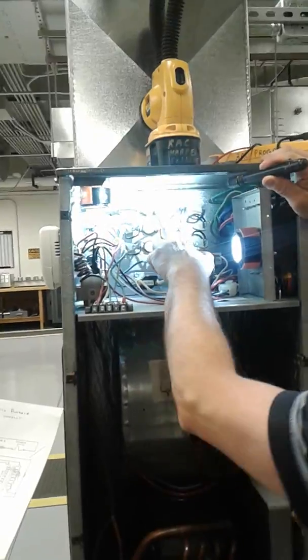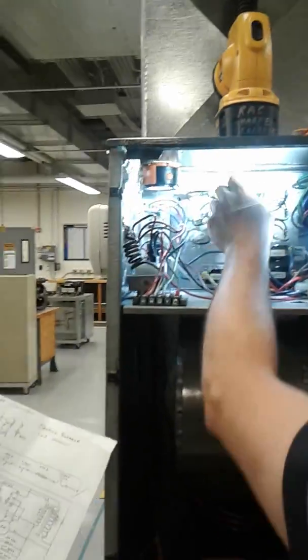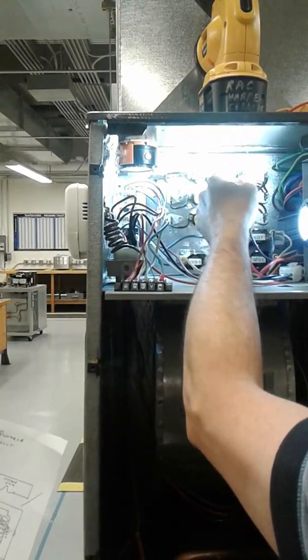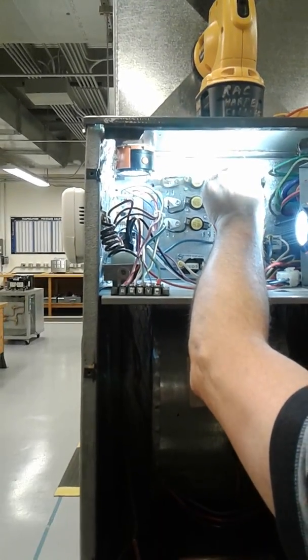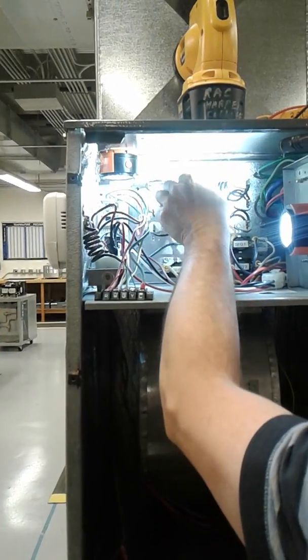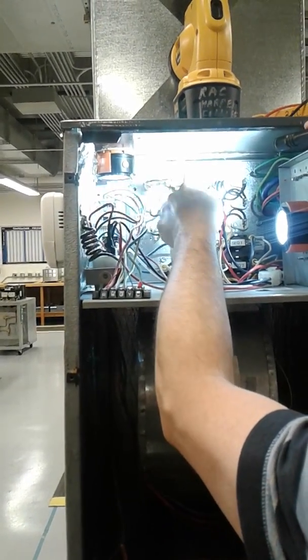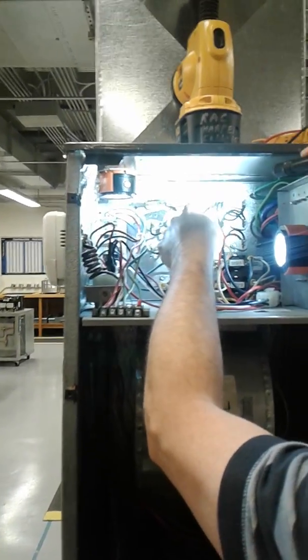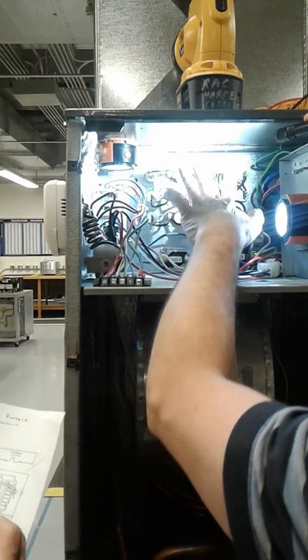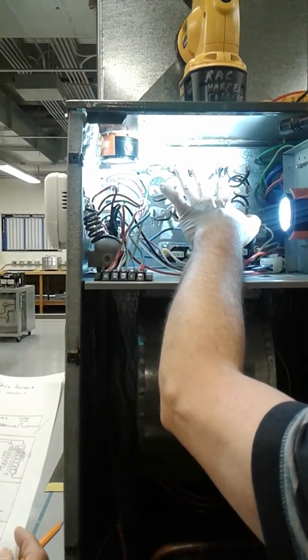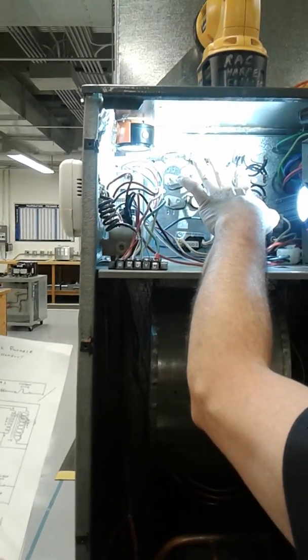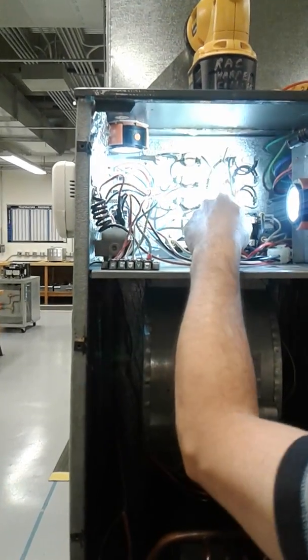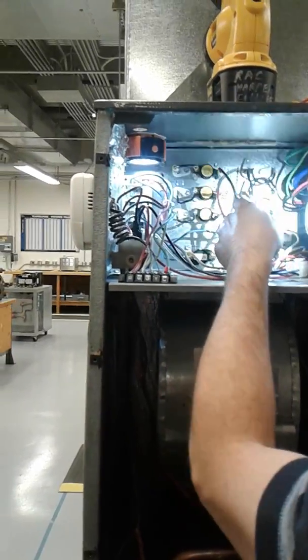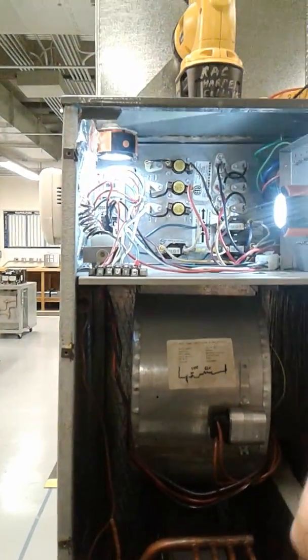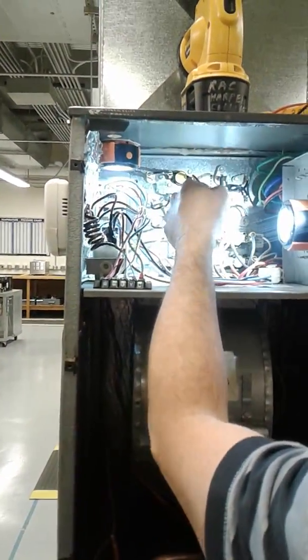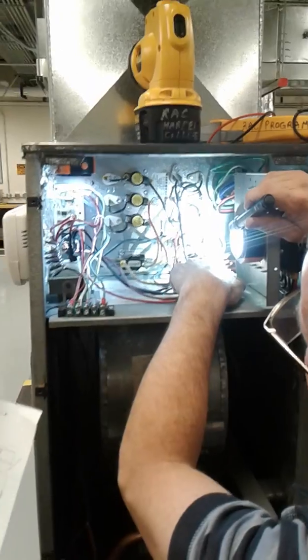Okay, now, the power that is entering element 1 are these two wires here, the two black wires. You've got 120 volts going in here to the fusible link, passing through the fusible link, going through the element. You have other 120 volts going in right here, okay? Being energized, going through the high limit, and then going through the coil. So 120 and 120 equals 240 volts to power that heating element, okay? Now, the power from the one side is coming directly from the breaker on the side. The other side, the power is coming from the breaker as well, but yet it plugs into the sequencer.